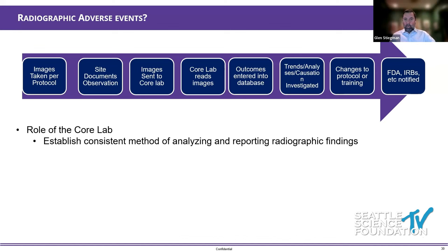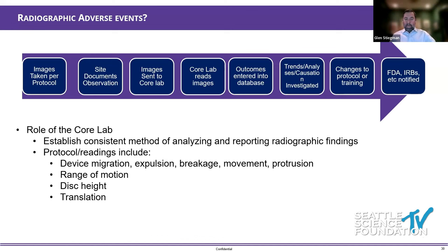And they read everything from the movement type observations, the range of motion, disc height translation, and even more. These protocols are really lengthy, but pretty much standardized for total disc. And these readings overrule whatever you guys are seeing or whatever the tech is seeing at the site. But it's certainly part of the story within the PMA itself or whatever the marketing submission is.